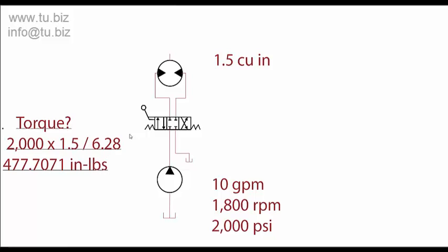If we need to increase the torque of this motor, one way to do it is by increasing the psi. If you increase the pressure applied to the same displacement, you're going to get higher torque. If you cannot increase pressure, then you need to go to a higher displacement motor.